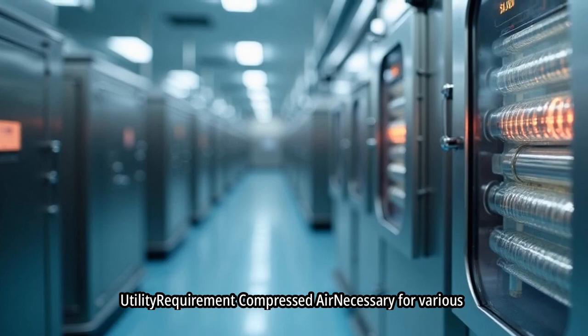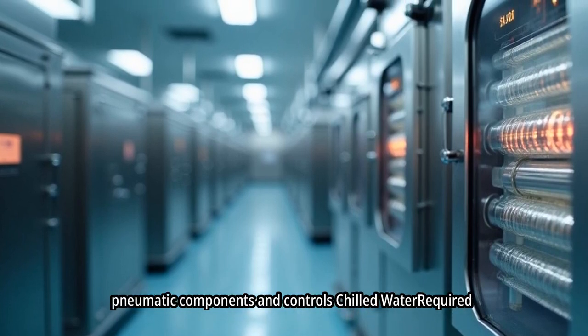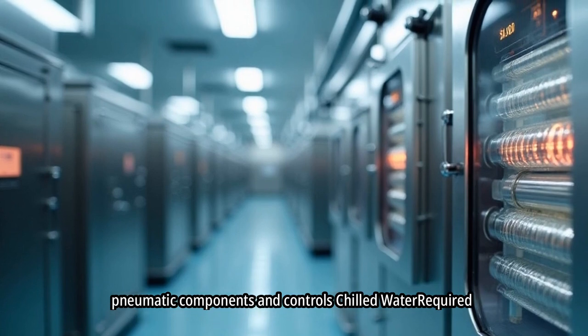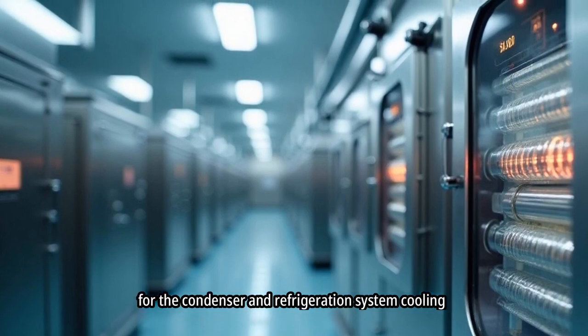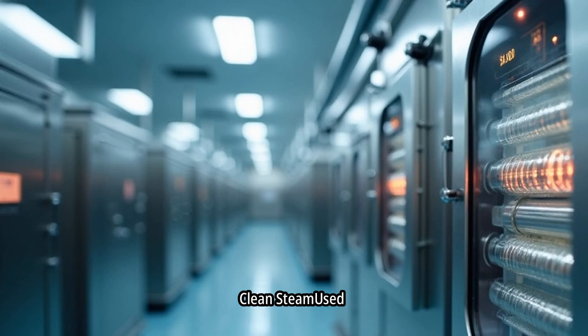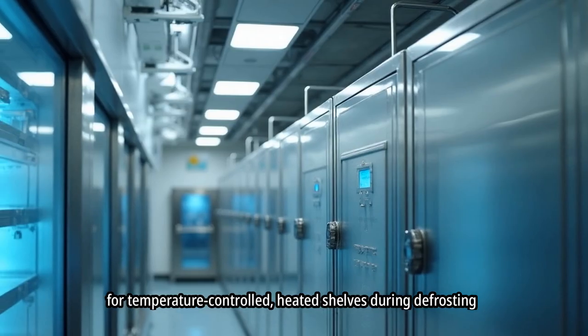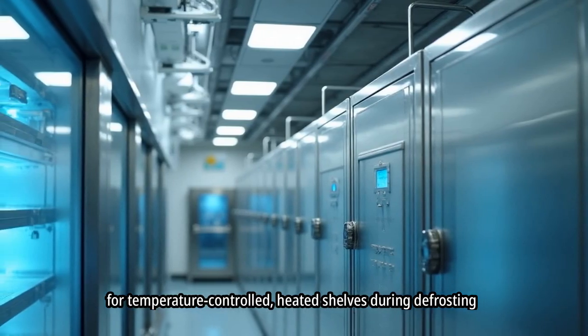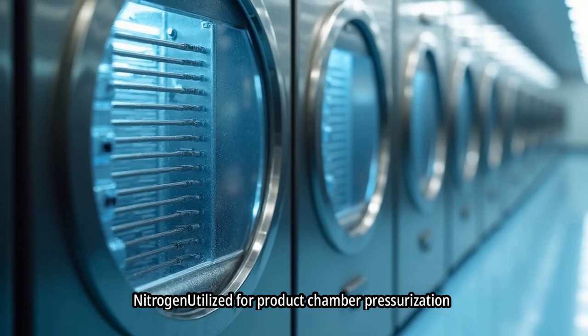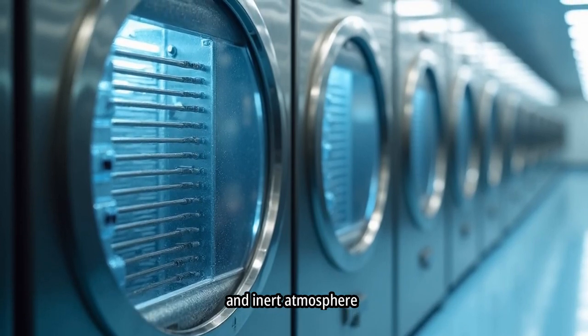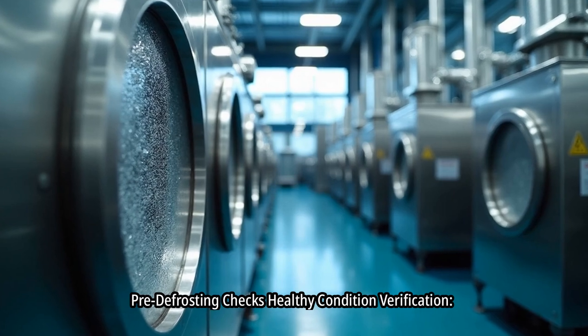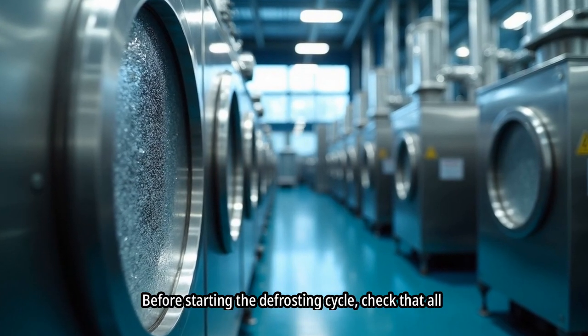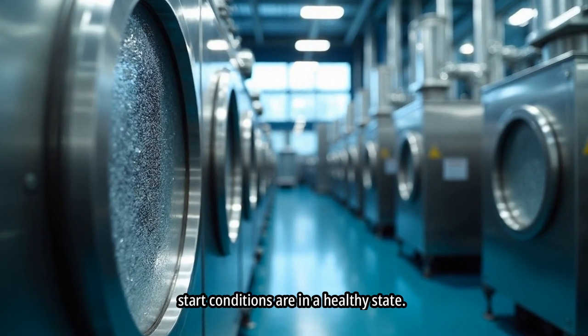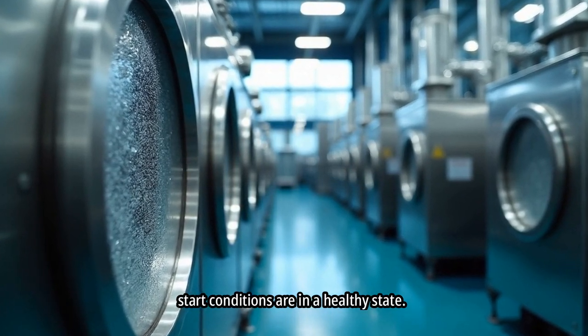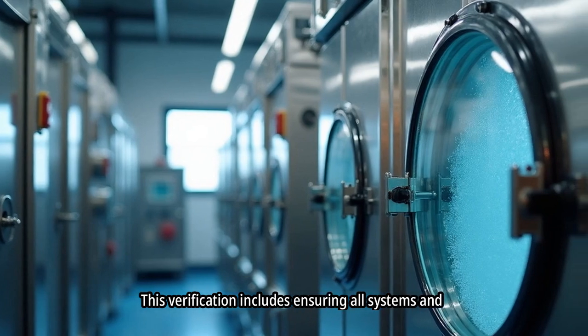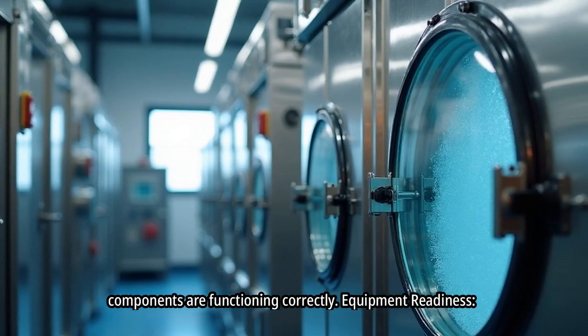Utility requirement: compressed air is necessary for various pneumatic components and controls. Chilled water is required for the condenser and refrigeration system cooling. Clean steam is used for temperature-controlled, heated shelves. During defrosting, nitrogen is utilized for product chamber pressurization and inert atmosphere. Pre-defrosting checks, healthy condition verification. Before starting the defrosting cycle, check that all start conditions are in a healthy state. This verification includes ensuring all systems and components are functioning correctly.